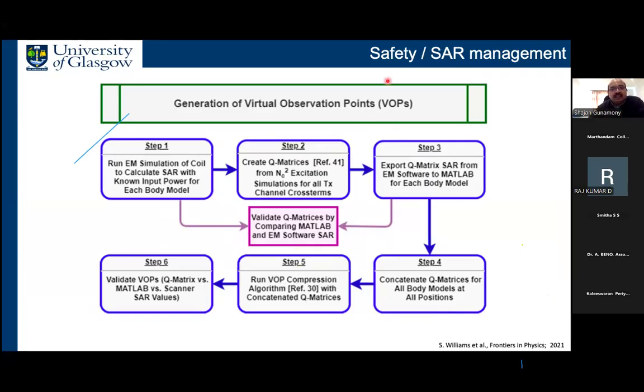In the Siemens system, the management of the power to the coil is managed by a method called virtual observation points. And in Glasgow, we were the first group outside of Siemens to implement this method. We generate a very accurate electromagnetic model of the coil in an EM simulation tool. Then we also simulate different body models, for example male and female of different age groups and sizes. These SAR values are then converted to something called a Q matrix, and all of these different simulations are concatenated into a single Q matrix.